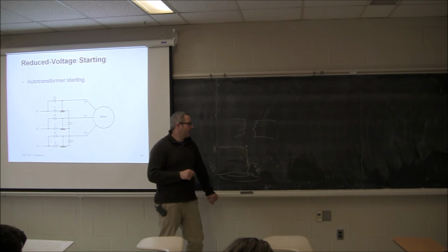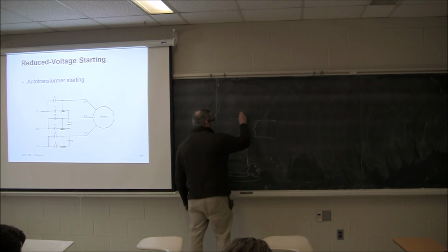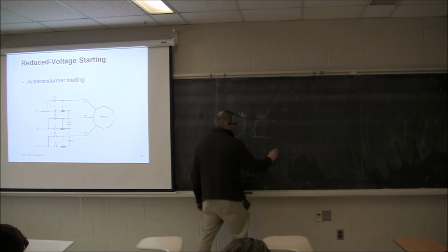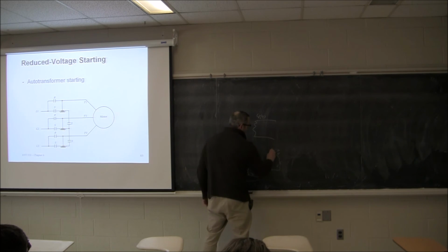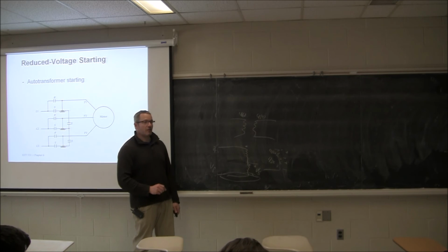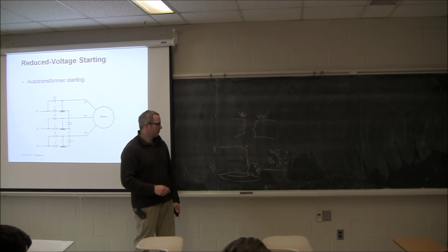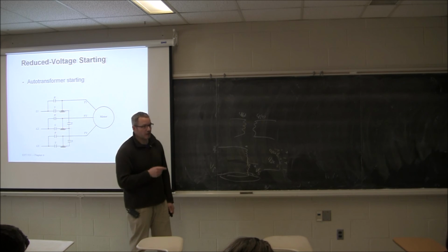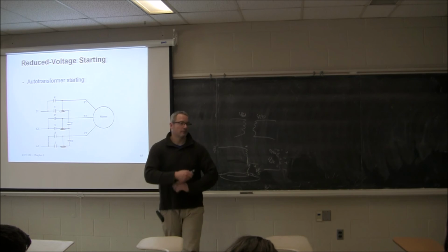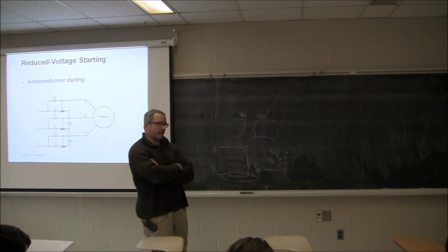It's really just adding. So like here, this is 4160 to 480, right? What if I took them and set them that way with a dot convention? Instead I get plus or minus, I can increase or decrease the voltage, can't I? That's all it is. They're just connected essentially in series. And then you boost or buck the voltage that way. And then it still is a matter of the number of windings, essentially. The turns of the winding, yep.